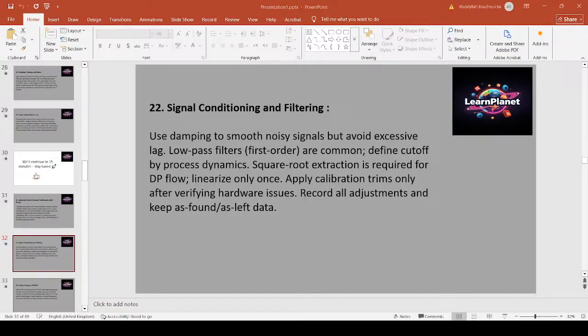Damping smooths noisy signals but introduces lag. Choose the filter time constant to preserve control performance. Low-pass filters are common. For DP flows, use square root extraction to linearize before control mode. Hardware conditioning, such as amplifiers, surge protection, and common mode rejection, is preferred to software-only fixes. Always verify the effect of filtering on loop stability during tuning. Example: when DP flow has pipe vibration noise, add a low-pass filter at the transmitter and re-evaluate controller tuning to avoid sluggish behavior.